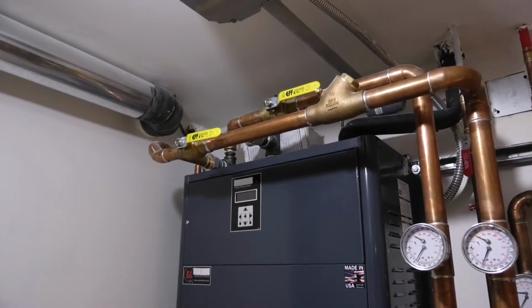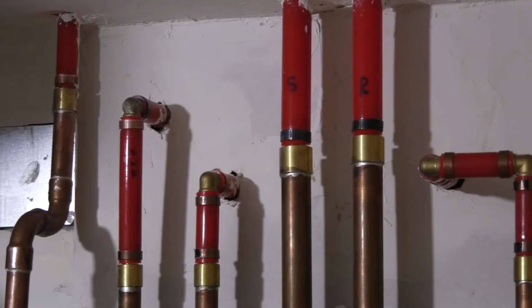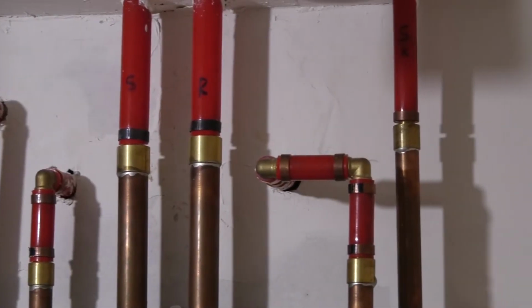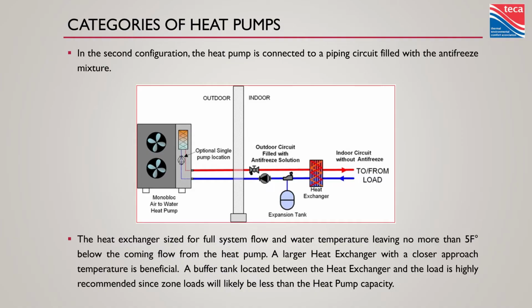Plus you're going to need another air separator, another expansion tank, another relief valve, some more makeup water, the list goes on. It may not save you as much money in glycol as you think, but it is going to make your heat pump less efficient every day of its life. So be careful with these systems, select your heat exchangers carefully.